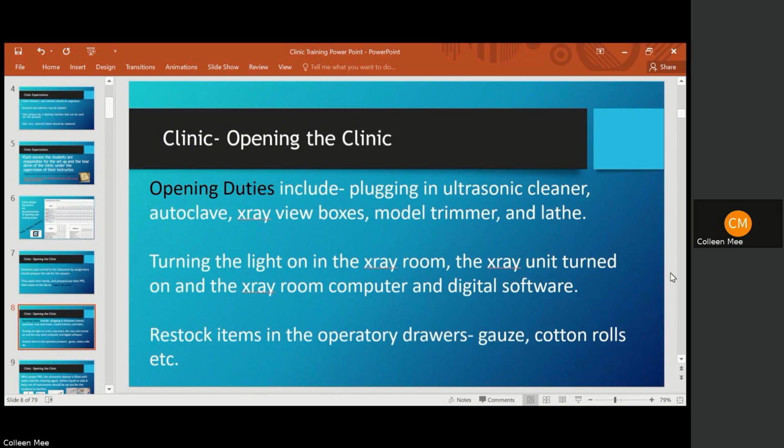According to the directions, the solution is very harsh. It will damage the lines. So it has to only be in there for a 24-hour time span, and then it must be flushed with water. So coordinate this so that it's done without fail every single week. We must document this. This is done in both chairs. And this is the document that you will use for that. This can be found in the curriculum shell as well. And you must record the completion of this.